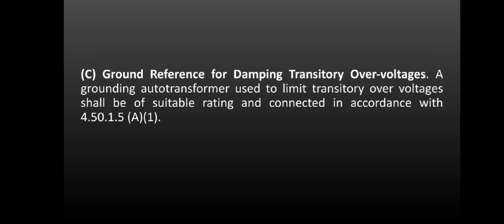C. Ground reference for damping transitory overvoltage. A grounding autotransformer used to limit transitory overvoltage shall be of suitable rating and connected in accordance with 4.50.1.5.